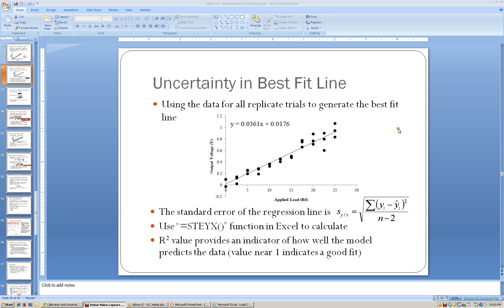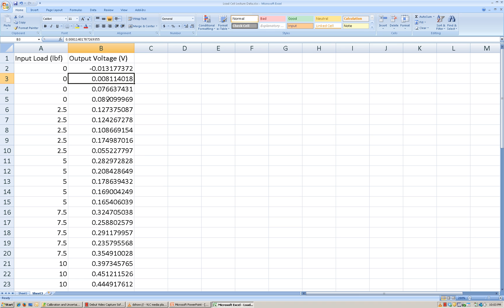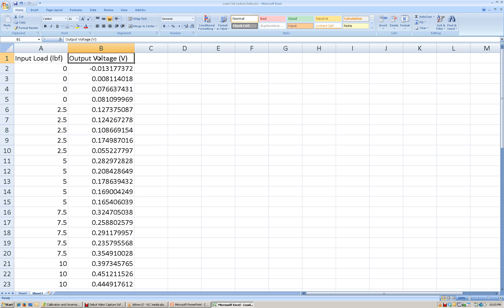In a previous video, I discussed how to determine the uncertainty in a best-fit line and how to come up with a best-fit line to a set of data. What I would like to do now is walk through an example to show you how we can do that. The example that I have is some made-up load cell data. The first thing that we want to do is look at the output voltage as a function of input load in Excel, and I want to plot the two of those.